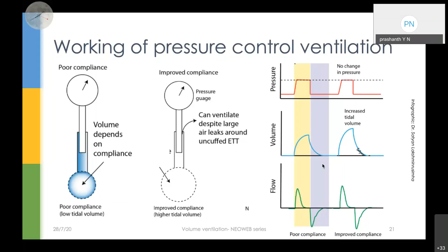So what we need to understand is that here we are setting the pressure. We are controlling the ventilation with the pressure. All we set is the pressure, not anything else. Based on this, the volume is increasing or decreasing. Even if there is some leak around the ETT tube, if you have improved compliance, a little bit of pressure is sufficient for you to inflate the lungs. These are the basic things you need to understand when we are talking about pressure controlled ventilation. All right.